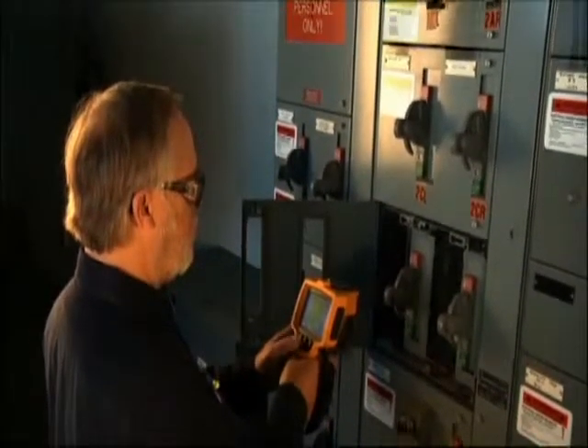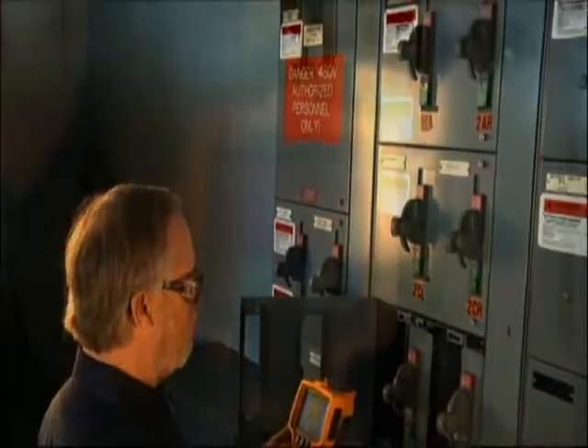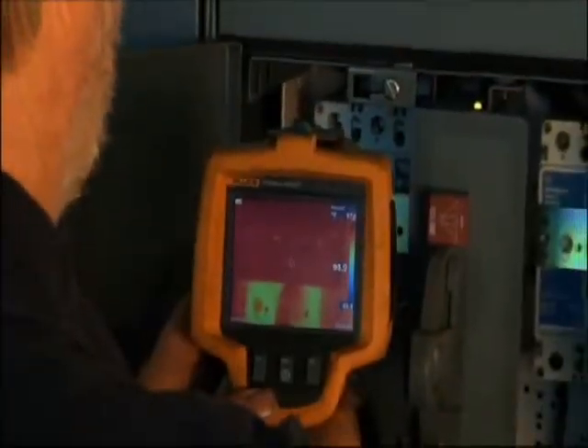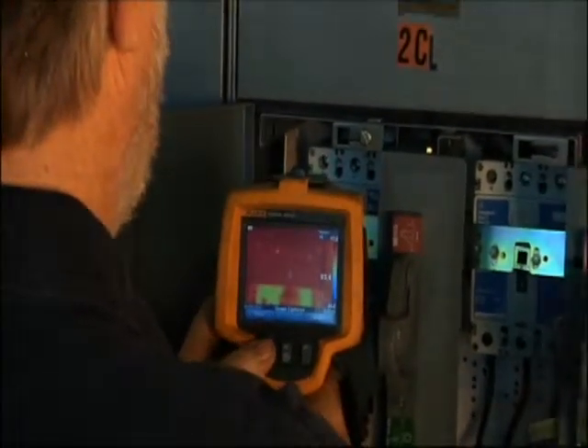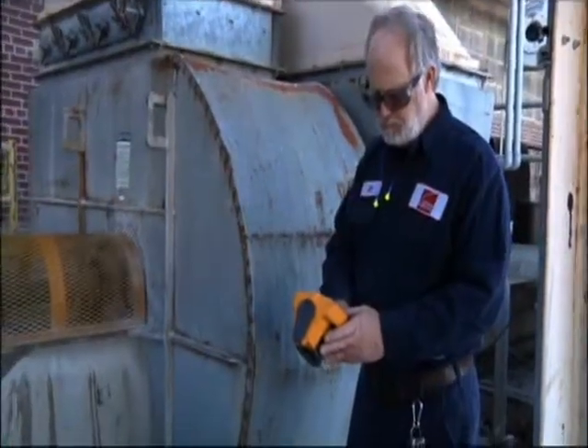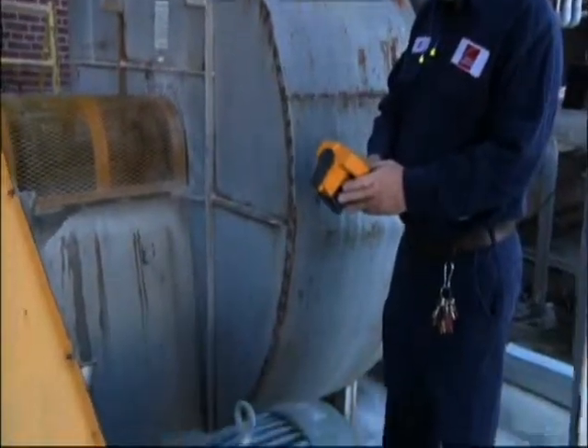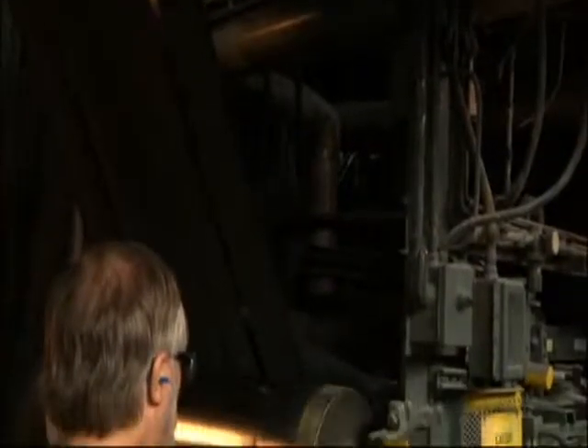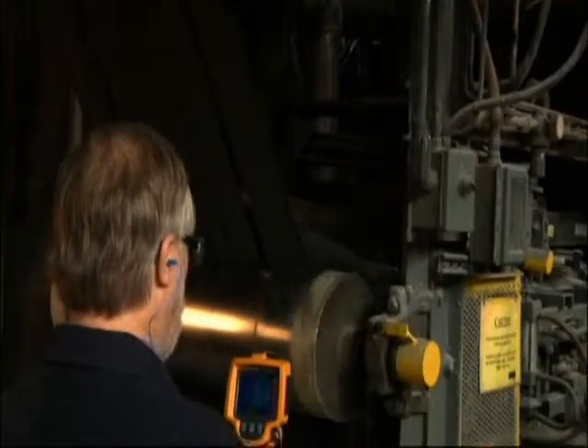A lot of people out there think that thermal imaging is electrical only. We shoot our motor control panels just like everybody else, but we also use it a lot in the mechanical aspect, looking for misaligned couplings, belts, and gear boxes.